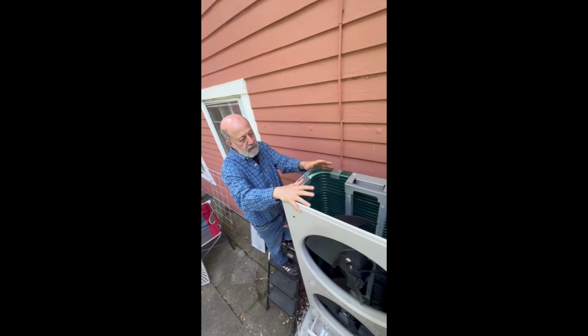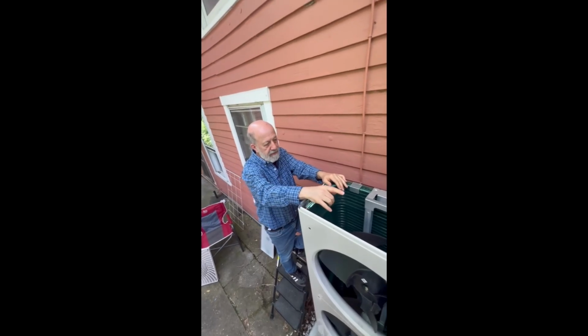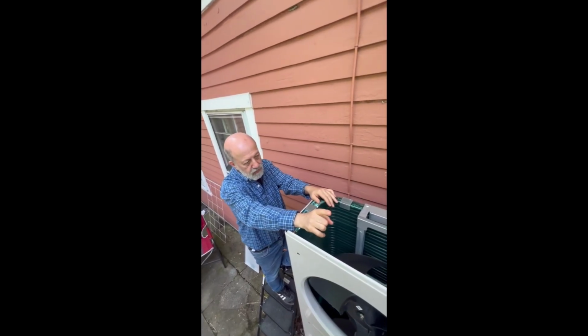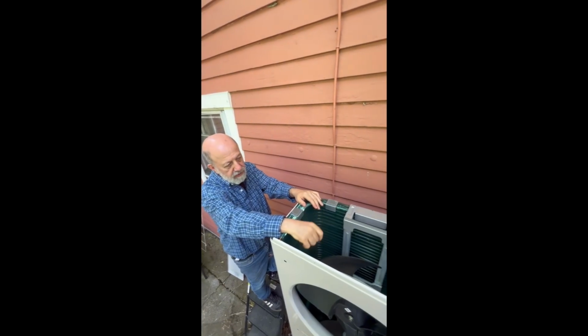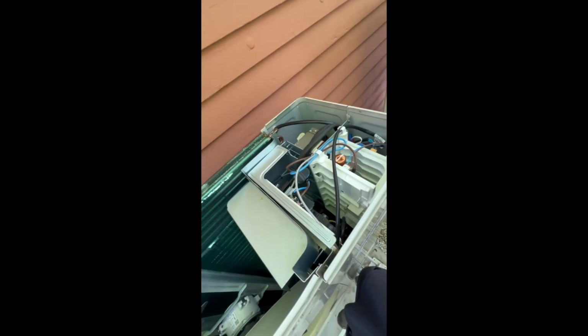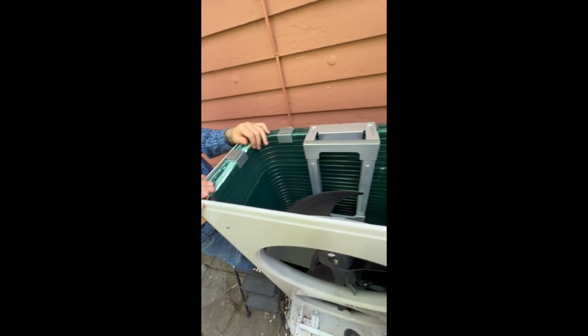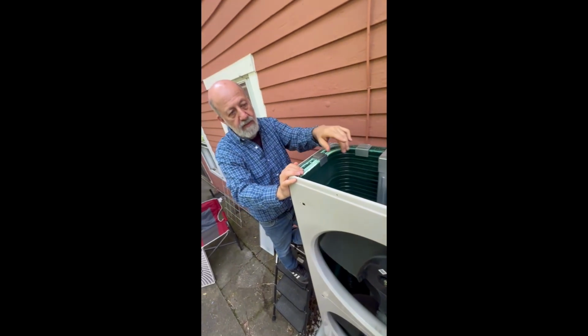The final general area of air bypass is from the outdoors into the control and compressor compartment at the end, and then from there into the fan section. And that turned out to be fairly substantial. And we will point out where it goes.